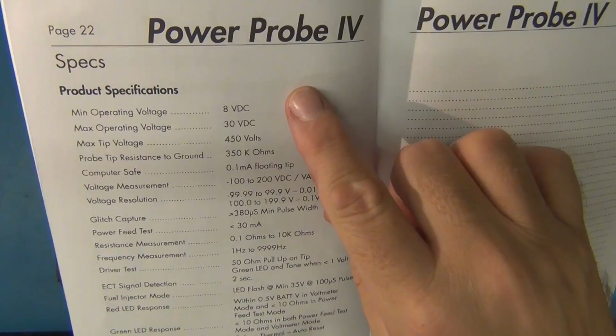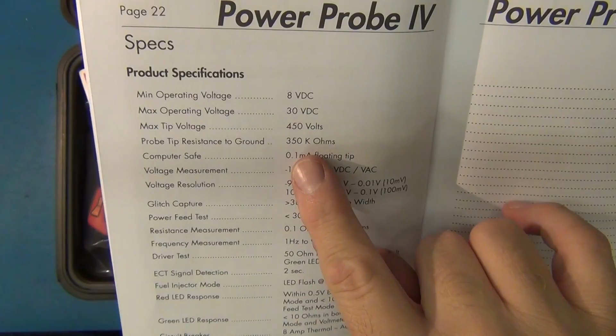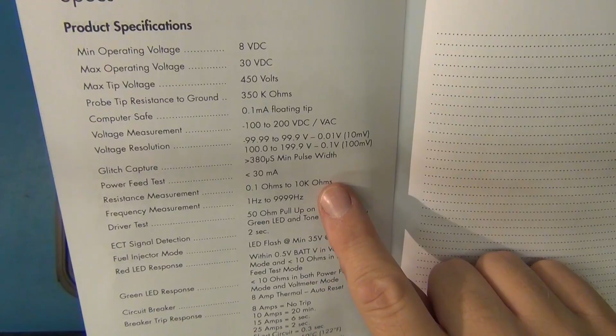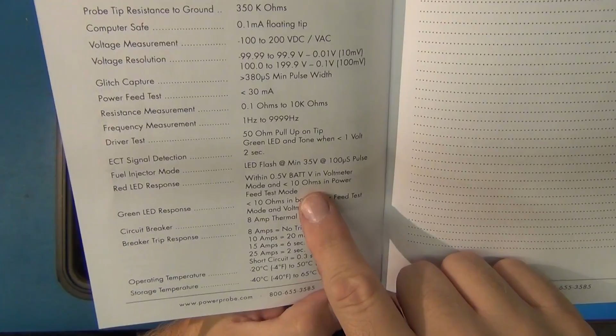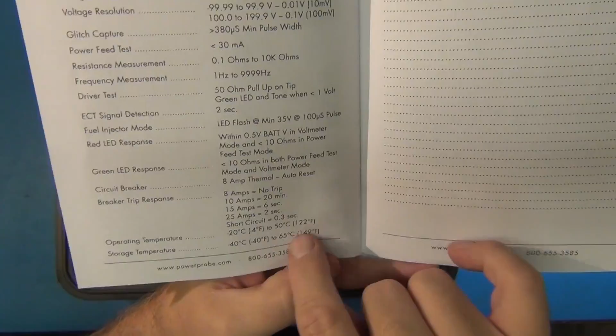That's also very nice. If you want to scan through this real quick, they go over some of the features. Looks like the tip resistance to ground is about 350 kilo-ohms—that's for voltage tests. You get a 50 ohm pull-up on the tip when doing the driver test, that's with the computer test. It talks about other things too, like when the lights come on and don't come on for responding circuits. You can do up to 8 amps, and it's thermal auto-resetting, which is nice—you can actually go up to 25 amps for 2 seconds without the thermal fuse tripping. Then some temperatures, a place to keep notes, and there you go.